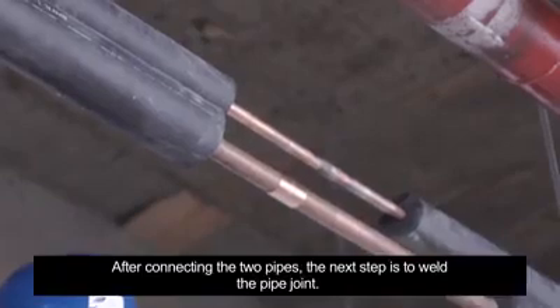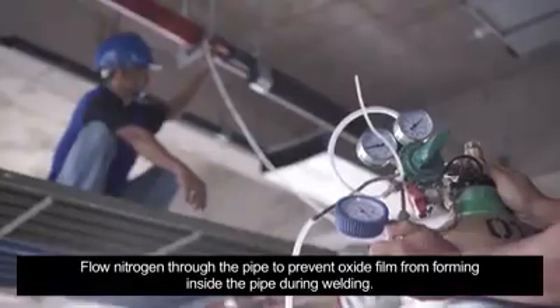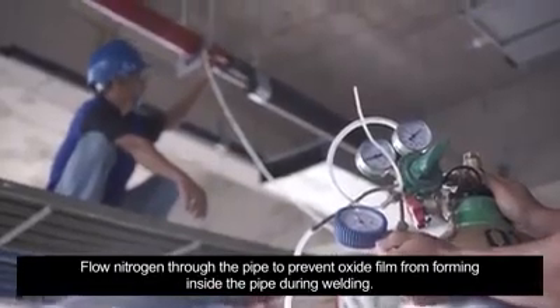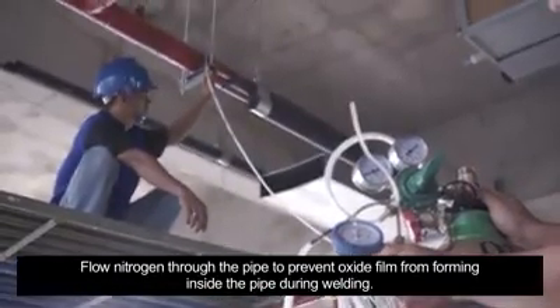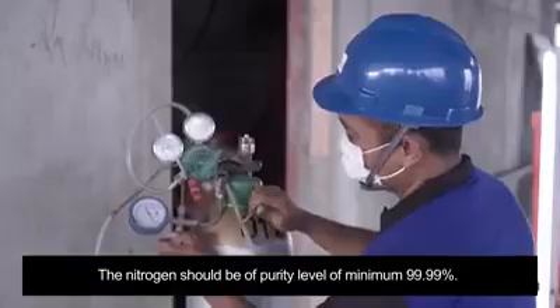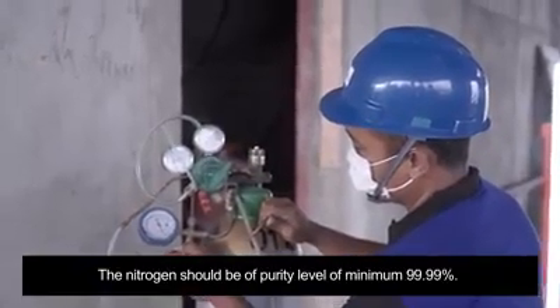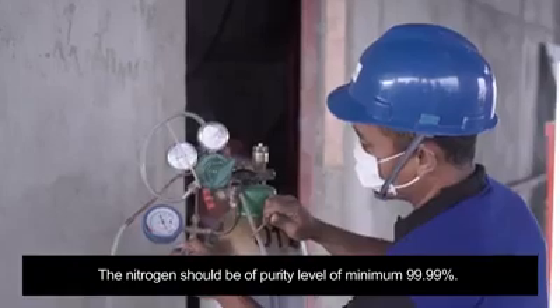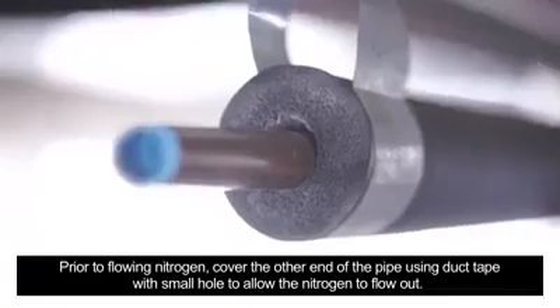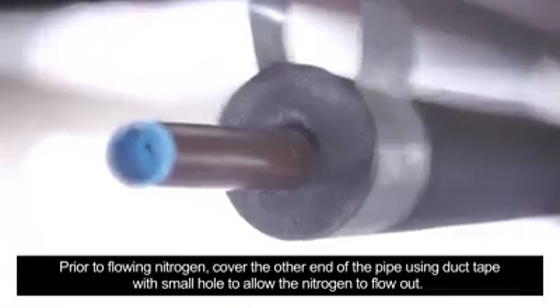After connecting the two pipes, the next step is to weld the pipe joint. Flow nitrogen through the pipe to prevent oxide film from forming inside the pipe during welding. The nitrogen should be of purity level of minimum 99.99%. Prior to flowing nitrogen, cover the other end of the pipe using duct tape with small hole to allow the nitrogen to flow out.